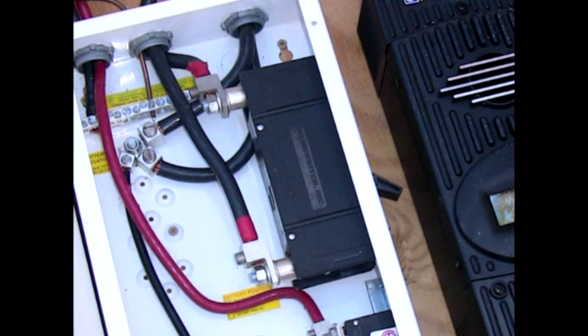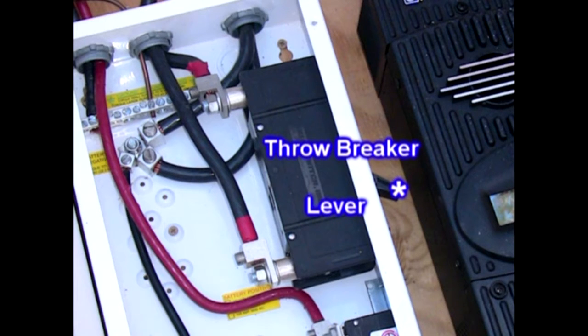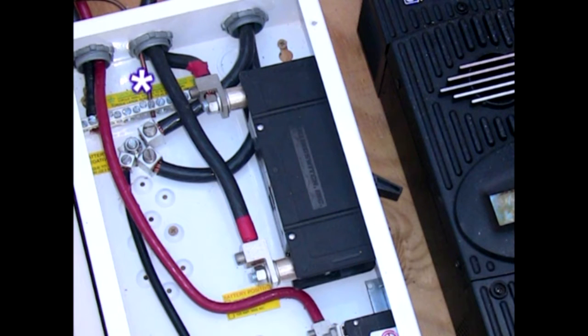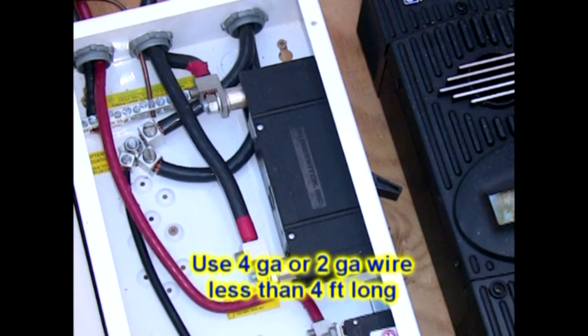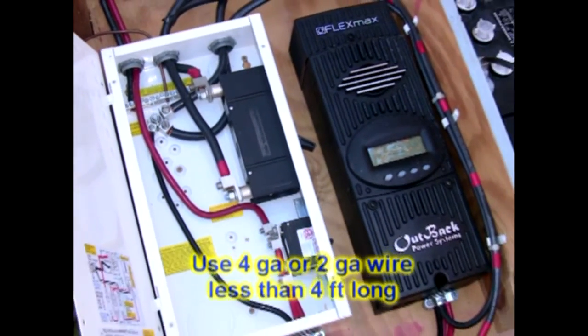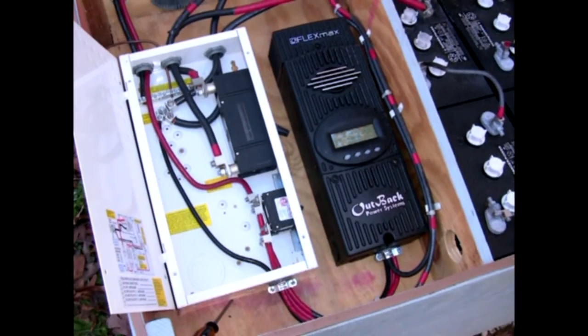This gives us the protection we need as far as the circuit breaker for the output of the batteries to the inverter, and it allows us to turn off the power from the batteries going to the inverter. The only remaining wire is our bare copper wire, which is connected to one of the ground posts on the top left, either the bar that we put the wire through and tighten it down, or the one with the lugs. Take it out of the box assembly completely and put it to our ground rod on the side of the battery box. And that concludes all of the basic wiring paths that we're seeing in this control box in this installation.